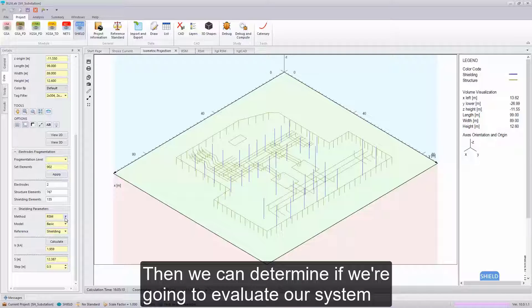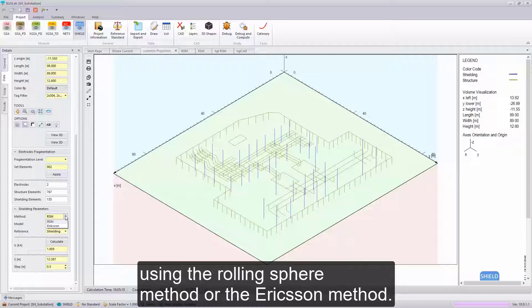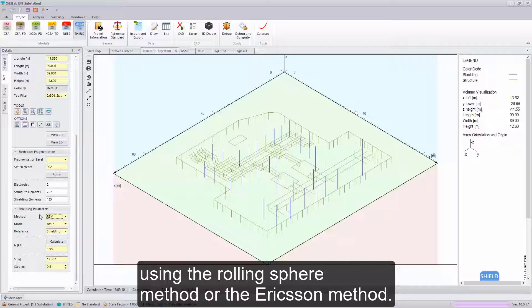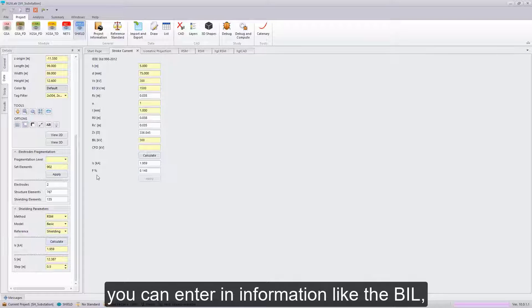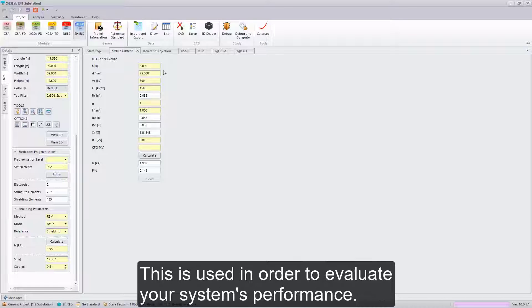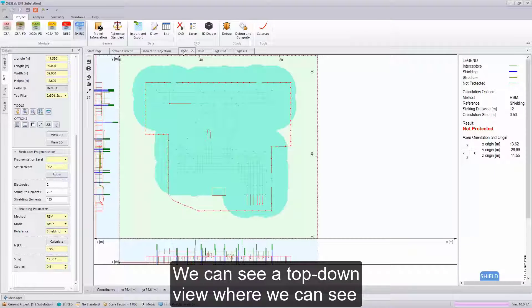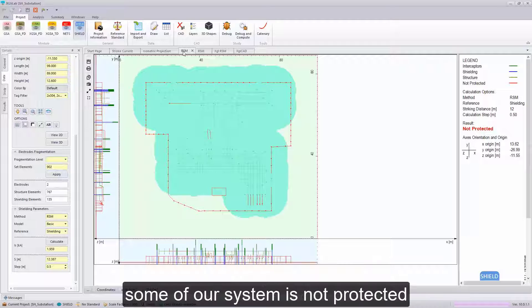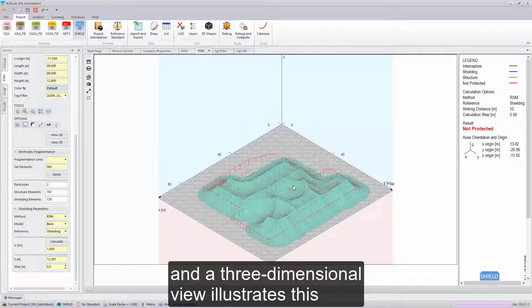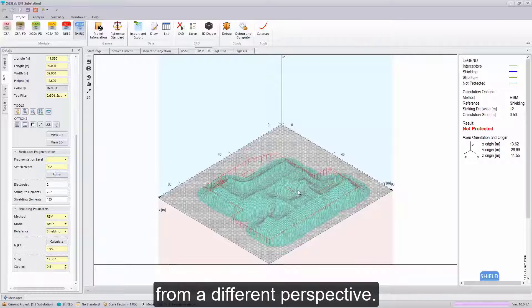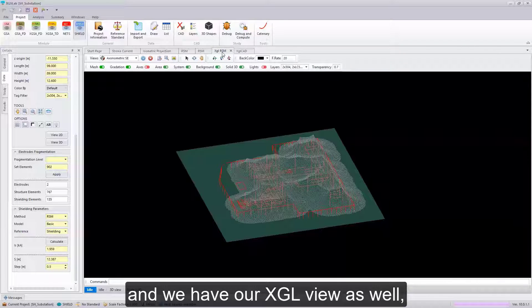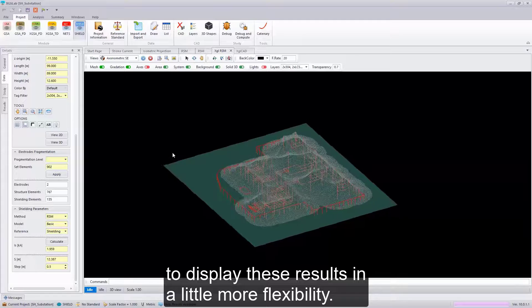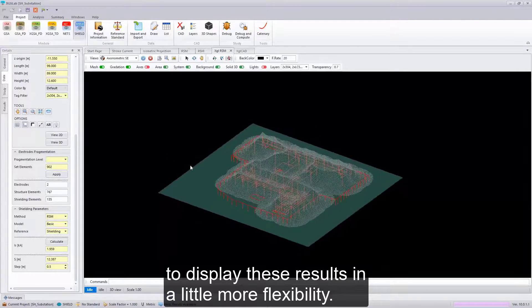Then we can determine if we're going to evaluate our system using the rolling sphere method or the Eriksson method. Hitting this calculate icon, you can enter in information like the BIL in order to calculate your striking distance. This is used in order to evaluate your system's performance. We can see a top-down view where we can see some of our system is not protected, and a three-dimensional view illustrates this from a different perspective. Again, red conductors representing non-protected objects. And we have our XGL view as well to display these results in a little more flexibility.